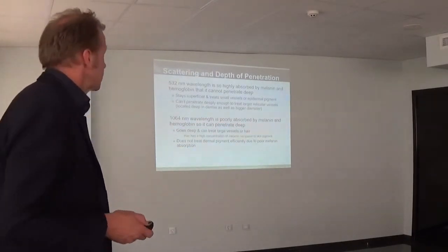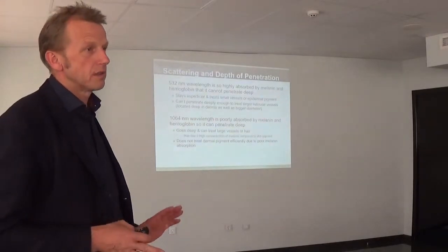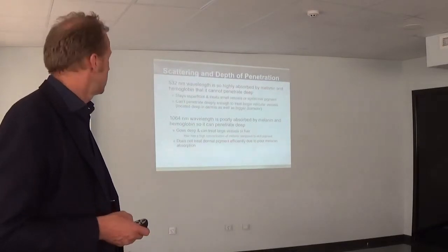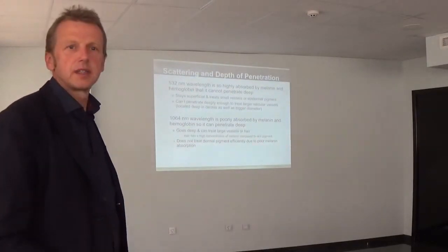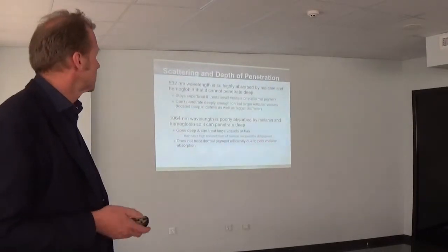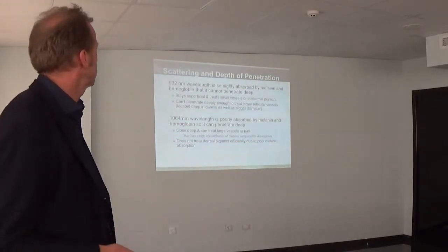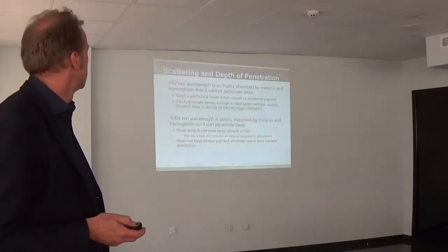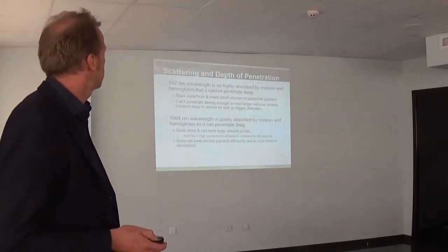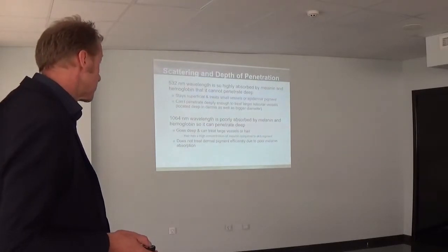532 also has a very high absorption in melanin. So for the darker skin types, it's a wavelength that needs to be treated with very much care because of this high melanin absorption. But that's the same with the limelight. So everything we said about limelight is a little bit applicable to this 532.